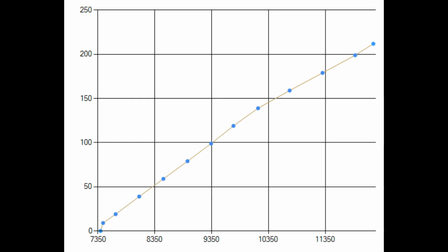What happens if the tank is 3 mm longer? The gauge curve will stretch upwards so that the top point coincides with the increased tank volume. What if the tank is 3 mm narrower? The calibration curve has to be compressed. What if the tank is 3 mm higher? You might get a slightly longer sensor. We have already considered this.